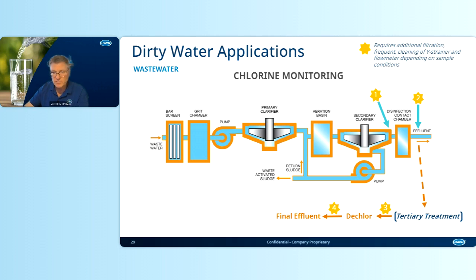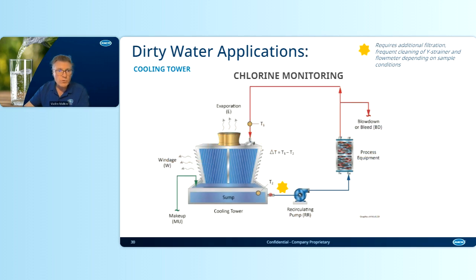And yes, we have some solutions for that. Most importantly, for this application, to ensure the concentration of chlorine is below the discharge limit or the permit level, the ULR version of the CL17SC can be used. All right, let's dive deeper into this pool of dirty water applications. This is a nasty application, very dirty water, because the cooling tower is exposed to the elements, and the water in the return cycle can be very nasty, very dirty. So this application will require additional filtration and more frequent cleaning of the strainer, filters, sometimes the flow meter, and the flow cell.